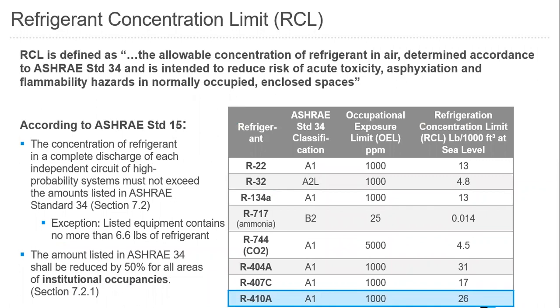And as you continue to look at the tables in ASHRAE 34 and then also look at ASHRAE 15, you'll see that there is a refrigerant concentration limit. And that refrigerant concentration limit, or RCL, is the allowable concentration of refrigerant in air as determined by ASHRAE 34. And this helps us make sure that we don't put too many toxic substances inside of an environment. So the concentration of refrigerant is defined by ASHRAE standard 15, whereas 34 defines the toxicity requirements.